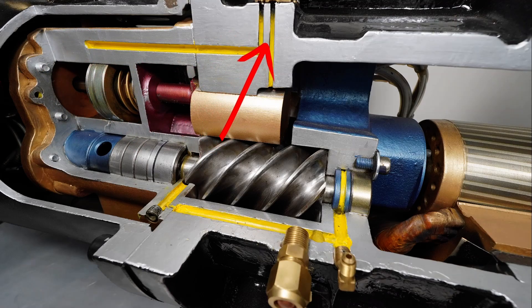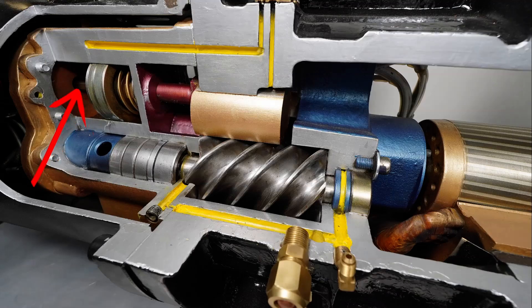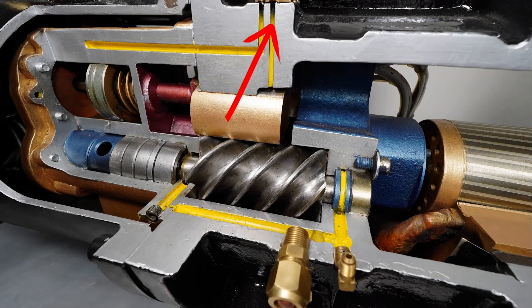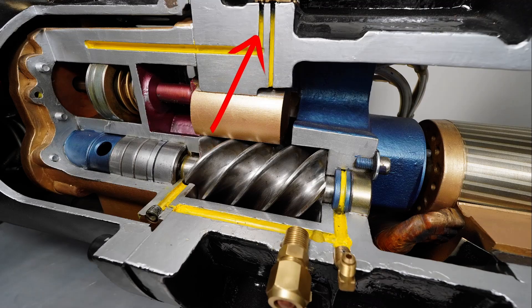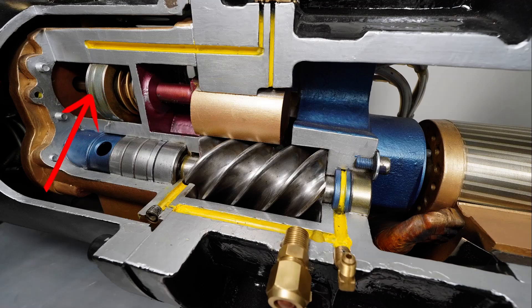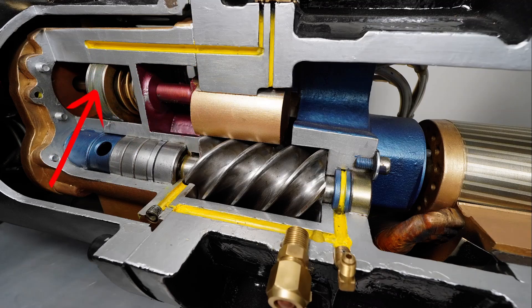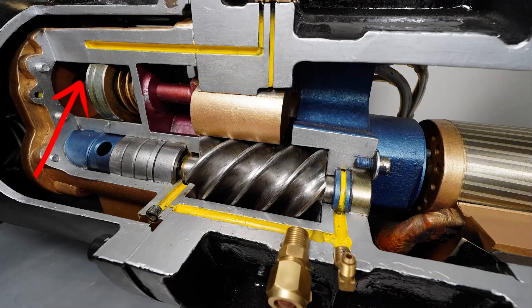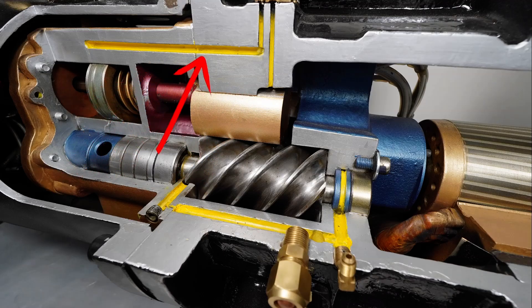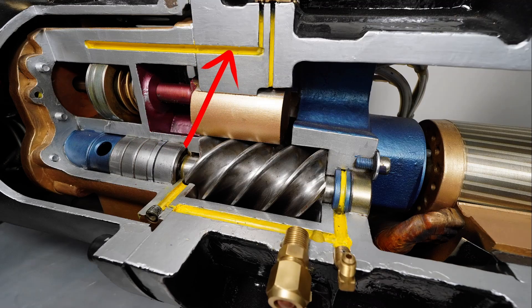There's a couple of different ways that these oil ports get ran. That's less important. Some of them will use a load and unload solenoid where we push more oil in to load it. We pull oil out to unload it. And then the slide just responds accordingly. Others will have like a staged or staggered solenoids. So there'll be one solenoid for 25%, one solenoid for 50%, one solenoid for 75% and one for a hundred percent capacity. And then we'll have just the unload solenoid from there. So as those solenoids engage and work, it'll step up and stagger the compressor staging based off of that solenoid that we trigger or fire. So that kind of depends on just the compressor manufacturer. Hanbells can do it both ways, just depending on which model you go with. A lot of manufacturers use a load unload, like Trane as an example, use a load and unload solenoid. So there's just two total. I would say that's probably the more common way I've seen that.